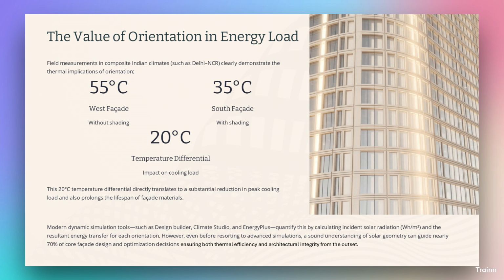This 20 degrees Celsius temperature differential directly translates to a substantial reduction in peak cooling load and also prolongs the lifespan of facade materials. Modern dynamic simulation tools, such as DesignBuilder, Climate Studio, and EnergyPlus, quantify this by calculating incident solar radiation, Wh/m², and the resultant energy transfer for each orientation. However, even before resorting to advanced simulations, a sound understanding of solar geometry can guide nearly 70% of core facade design and optimization decisions, ensuring both thermal efficiency and architectural integrity from the outset.